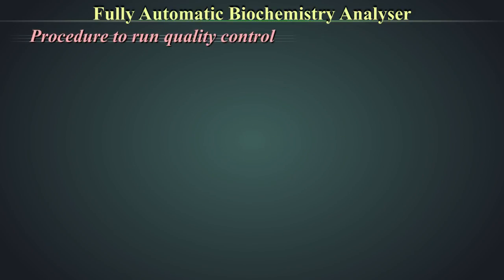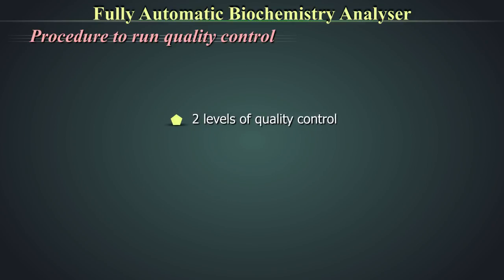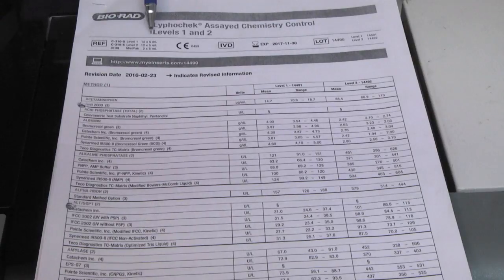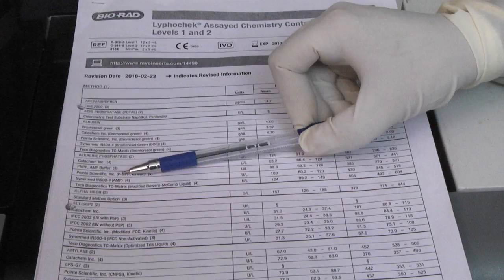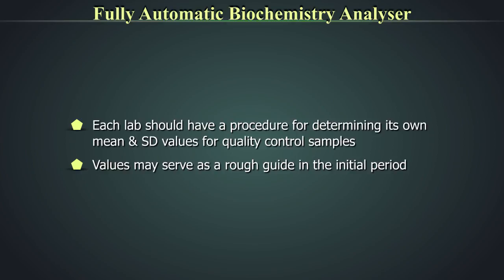Quality control should be run daily as routine for all analytes being tested, also after an analyte is calibrated, after reagent lot change, and after major maintenance activity. At least two levels of quality control should be run — a normal level and an abnormal level. The quality control kit insert contains the lot number, expiry date, mean values, and standard deviation limits for all analytes. Define the quality control in the machine and run it. Each lab should have a procedure for determining its own mean and standard deviation values for quality control samples; manufacturer values may serve as a rough guide initially.